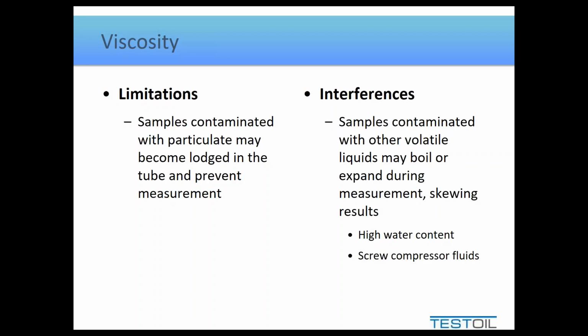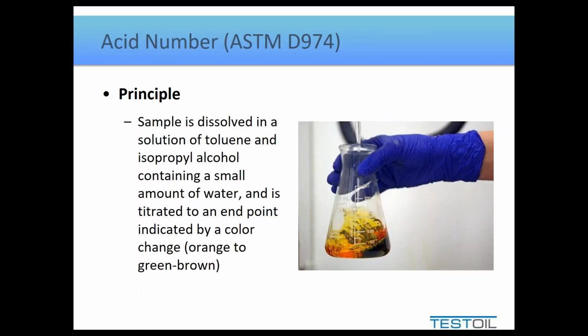So I don't really concern myself with the fact my viscosity might not be an accurate measurement when I have a lot of water content, because I know what's driving that water content. But there's more to it than that. So before I get to water content, let me talk about acid number.